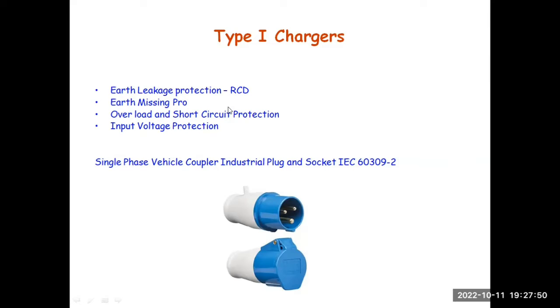Normally, type 1 or type 2 chargers have earth leakage protection called RCD, residual current detection, and earth missing protection. This is one of the main protections required by the standard. So any charger, whether type 1, type 2, or even DC fast charger, should have earth leakage protection sensing and earth missing protection. Safety is a very high priority criteria in charging applications - the safety of the personnel using it is given more preference.